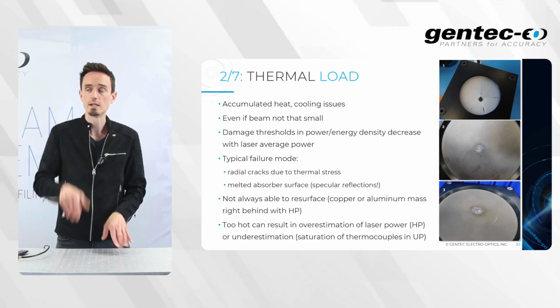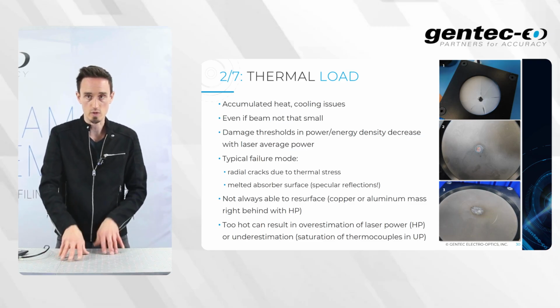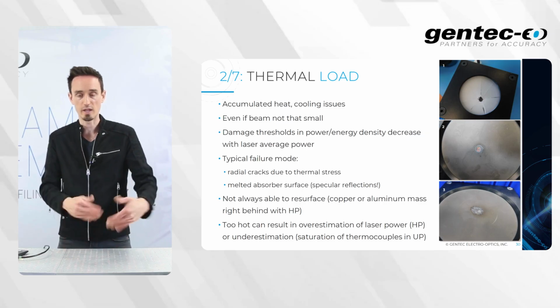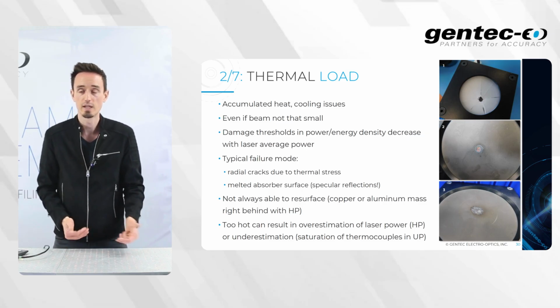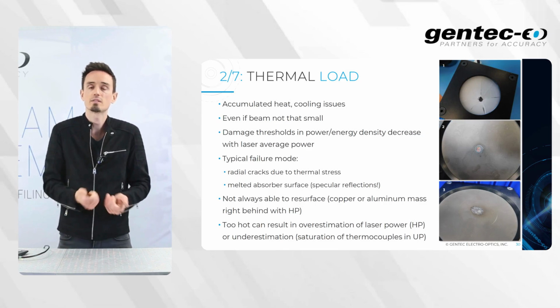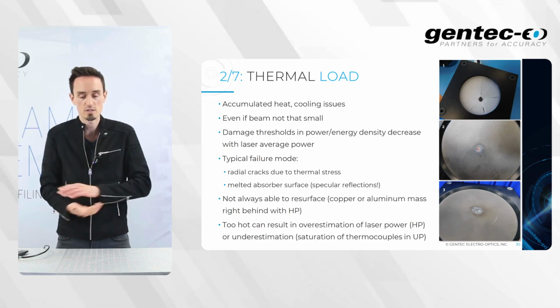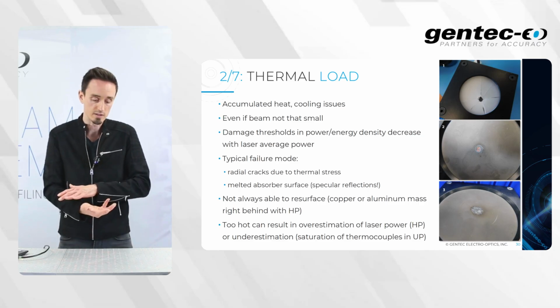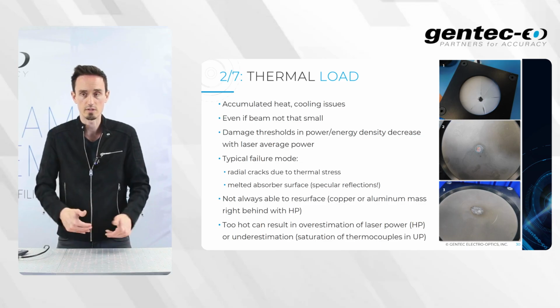If you take 2 and 3, those are water-based calorimeters where we use either copper or aluminum masses right behind the absorber itself. And as you can see, the mass started to melt, so we cannot replace that easily. We need to change the entire surface and the metallic mass underneath.